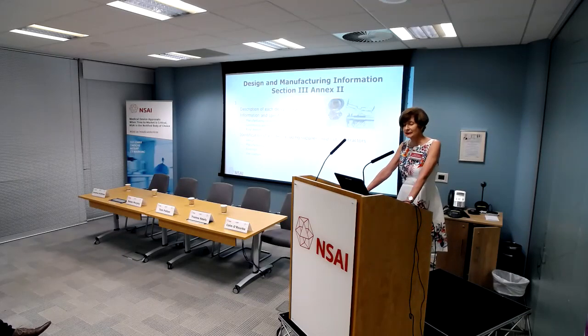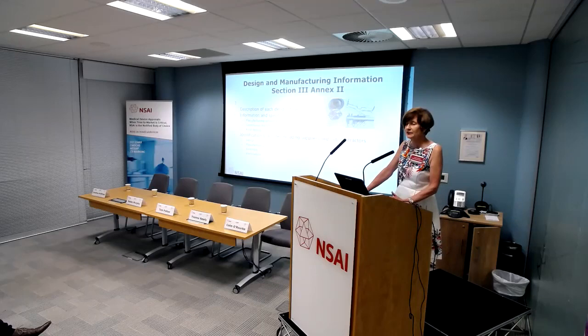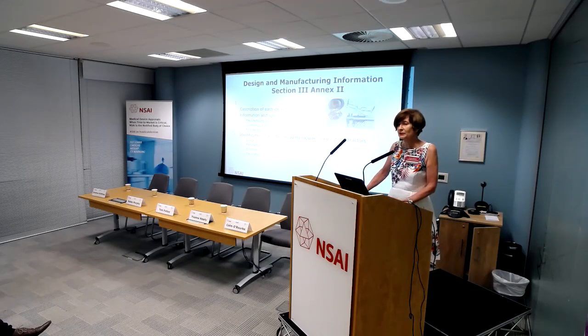So what exactly do we need there? So we need a description of each design stage, not just the overall. You have to go into each specific design stage. The information on specifications, the manufacturing processes and their validations. It is not sufficient to provide the notified body with a protocol. We'll throw it back at you. We need to see the validation. The protocol should tell us how you do it. The validation is the result, and that's what we need to see.